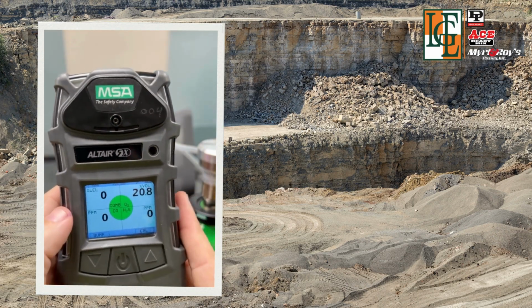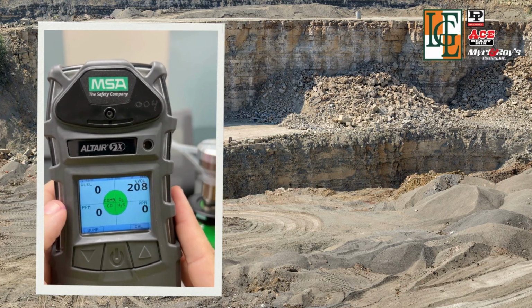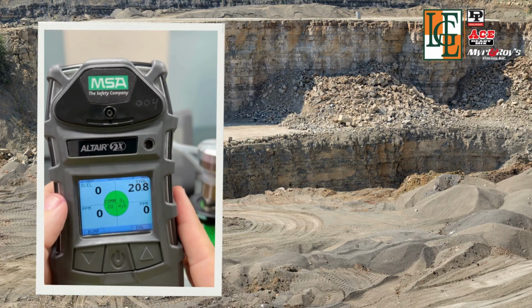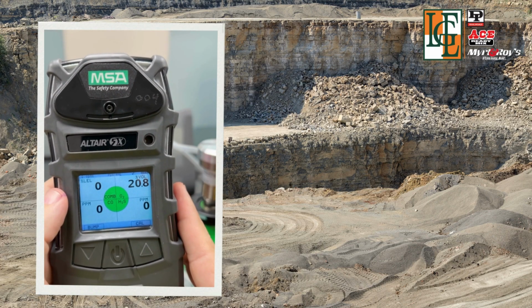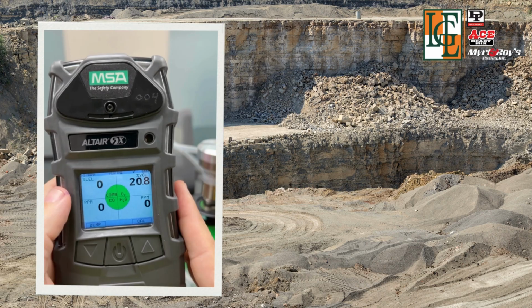All right, so that's how we've calibrated this MSA Altair 5X, and we also completed the bump test. Calibration should be completed at least once every 6 months, and then bump test on a daily basis.